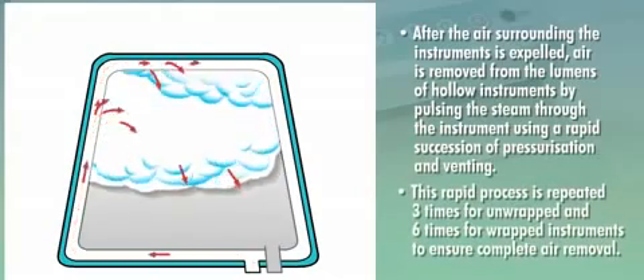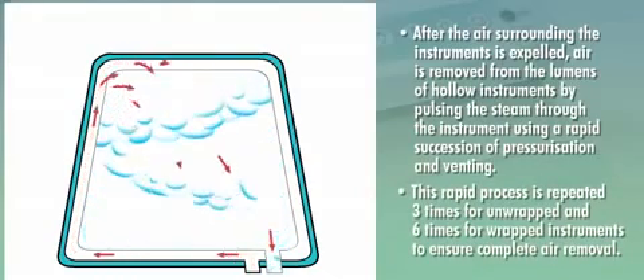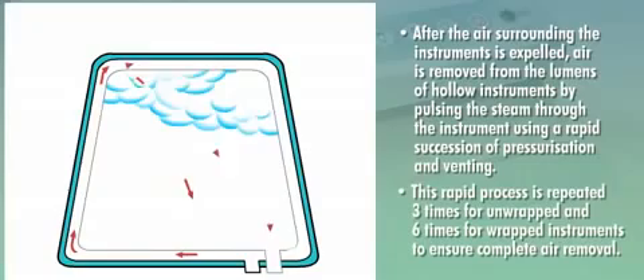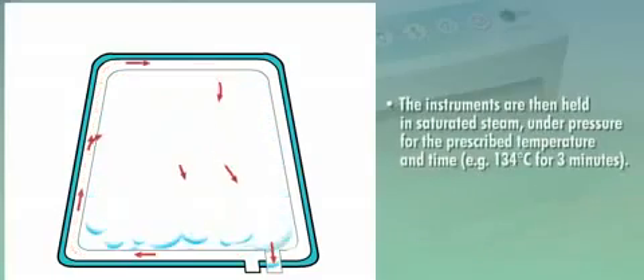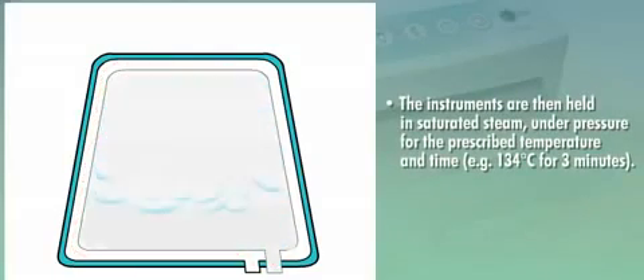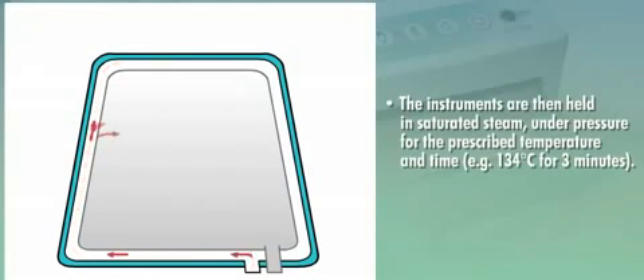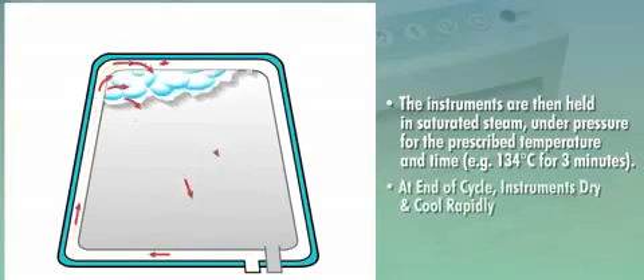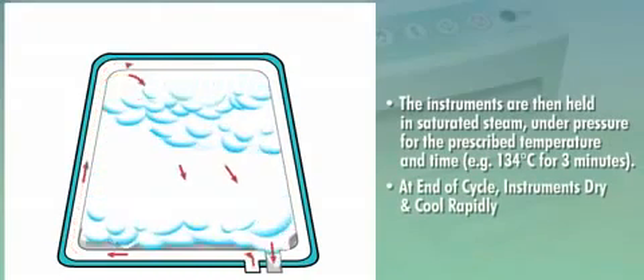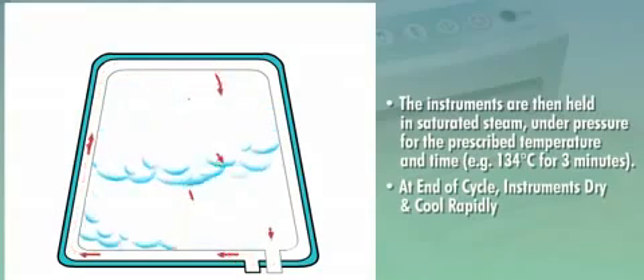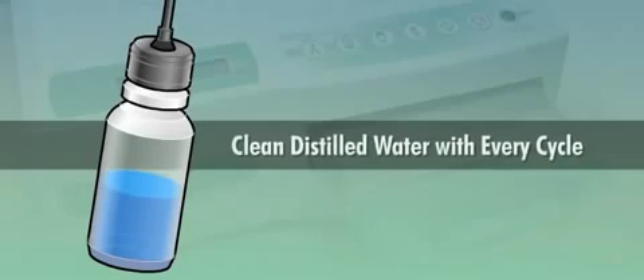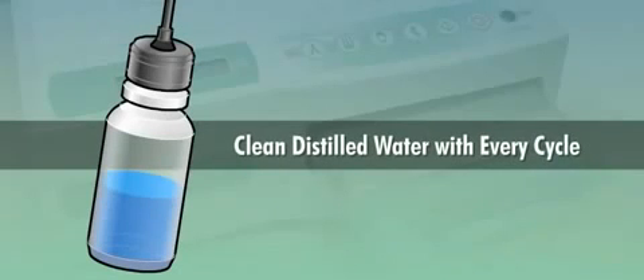This rapid process is repeated 3 times for unwrapped and 6 times for wrapped instruments to ensure complete air removal. The instruments are then held in saturated steam under pressure for the prescribed temperature and time, for example 134 degrees Celsius for 3 minutes. At the end of each cycle, when the machine has vented, a small compressor switches on, drying and cooling the instruments rapidly. The STATIM cassette autoclaves use clean distilled water with every cycle, preventing the buildup of handpiece lubricant and other water contaminants. Here are some commonly asked questions.